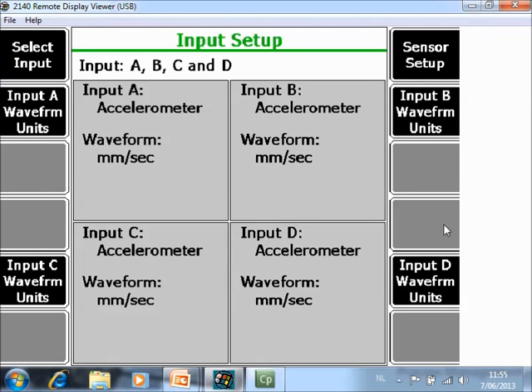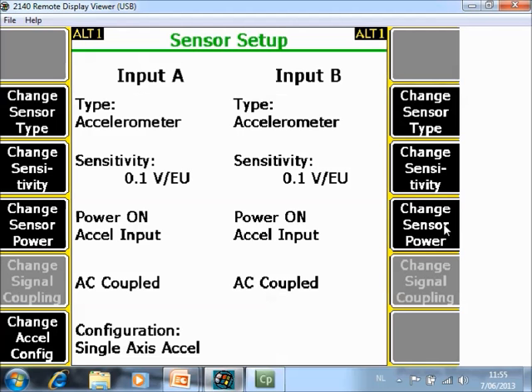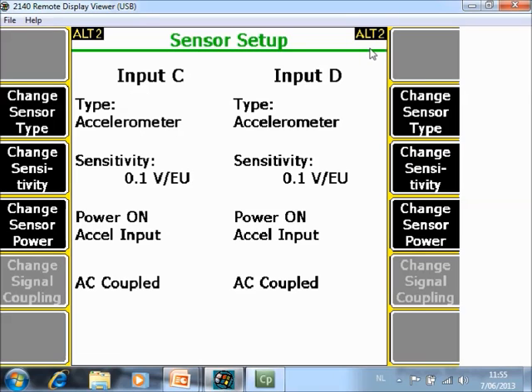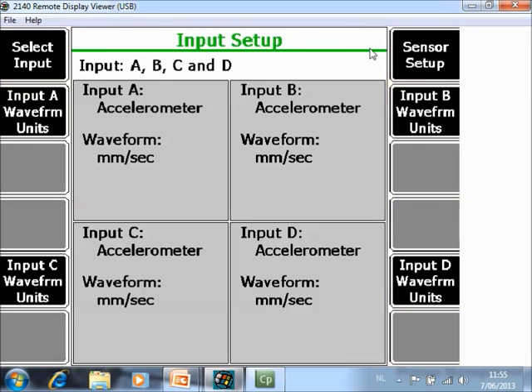The kind of sensors that you are using have to be specified in F7 Sensor Setup. In this example we are using an accelerometer, 100 millivolt per engineering unit and power ON. So this is a normal standard accelerometer on input A. Input B is the same. Go to ALT 2 to check channel C and D if you want to do 3 or 4 channels. So the 4 channels are correctly configured. You can continue with pushing ENTER.